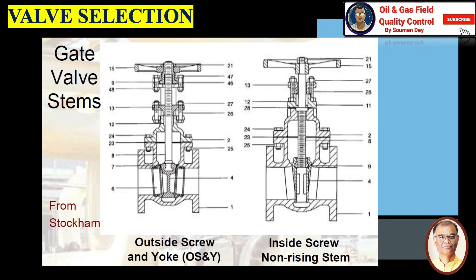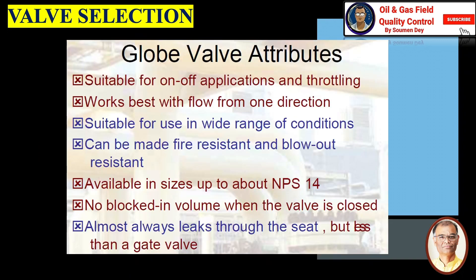Gate valve stems: outside screw and yoke (OS&Y), and inside screw non-rising stem shown on the right side. Now, globe valve: it is suitable for on and off position and throttling, works best with flow from one direction, more or less like a check valve, suitable for use in a wide range of conditions, can be made fire resistant and blowout resistant, available in sizes up to NPS 14.